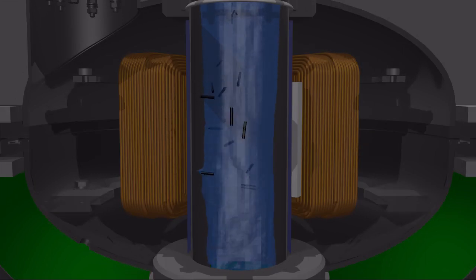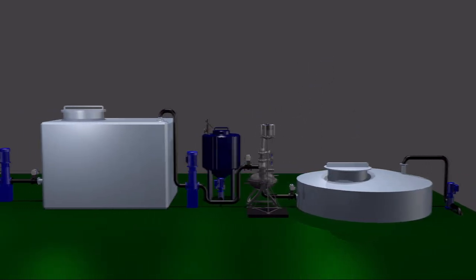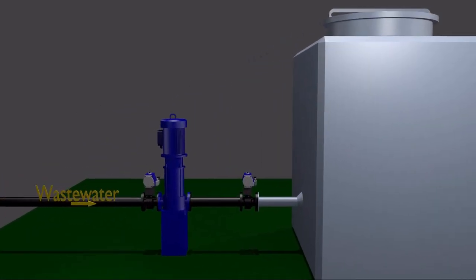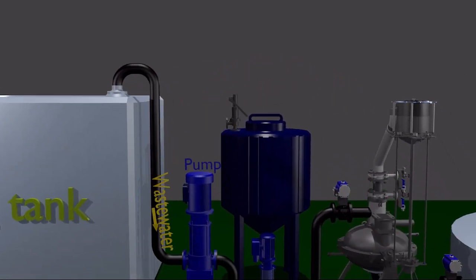Using the AVS for wastewater decontamination allows reduction of reagent and power consumption, decreases equipment footprint, and improves the quality of the decontamination process. The process in the AVS mill occurs in one stage; therefore, equalized wastewater is pumped directly into the AVS together with lime milk from the consumption tank.